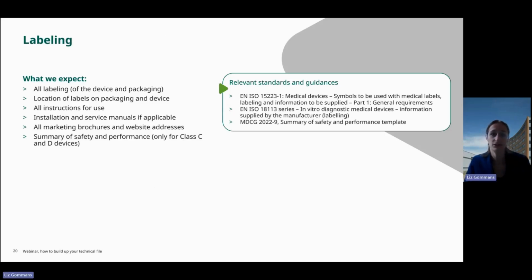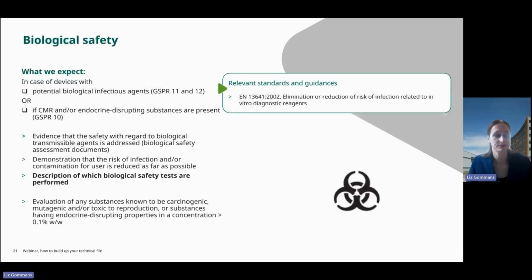And if you have a class C or D device, the SSP. There is the guidance, it's listed on the right here, MDCG 2022-9, which is the SSP template. We also expect to see that one.